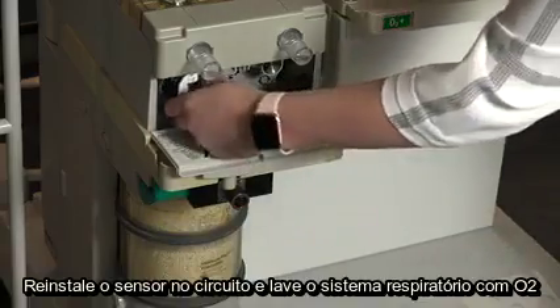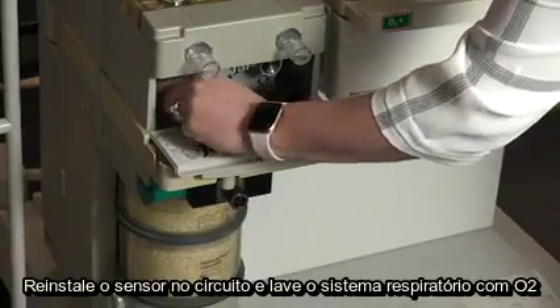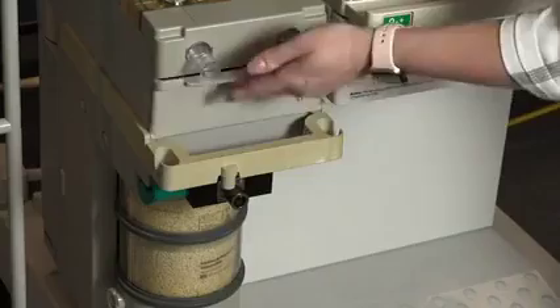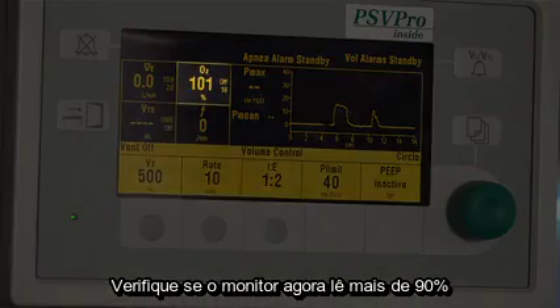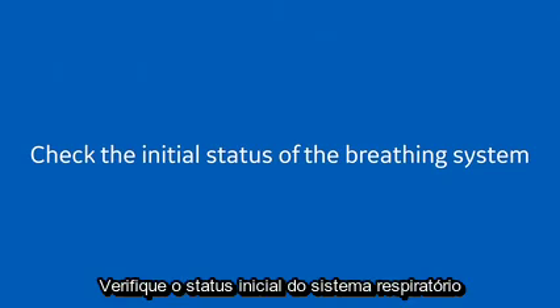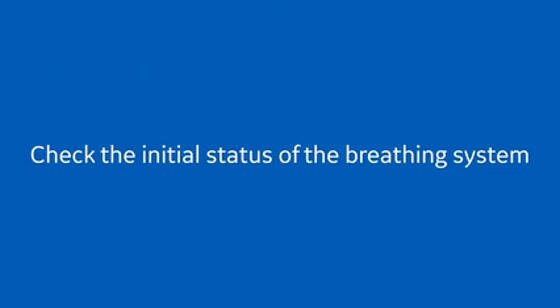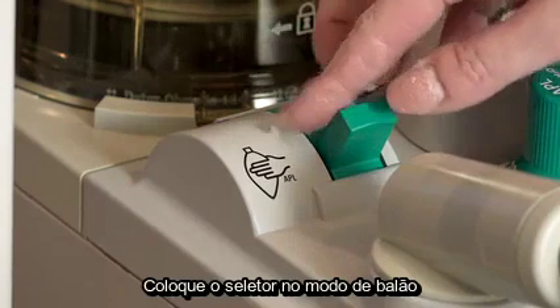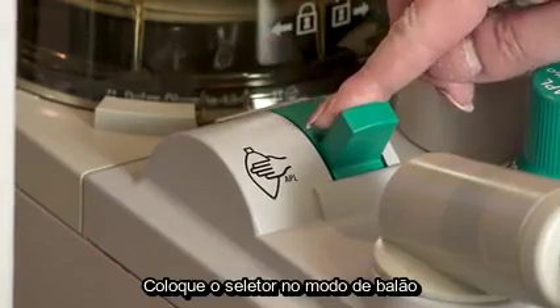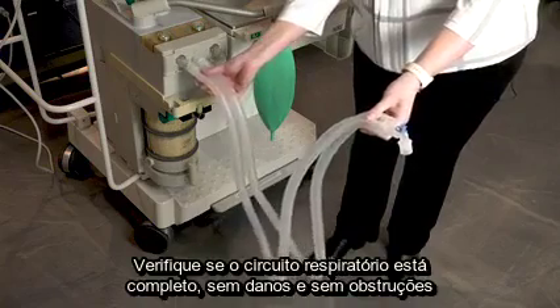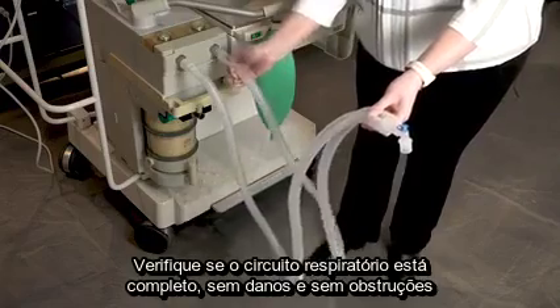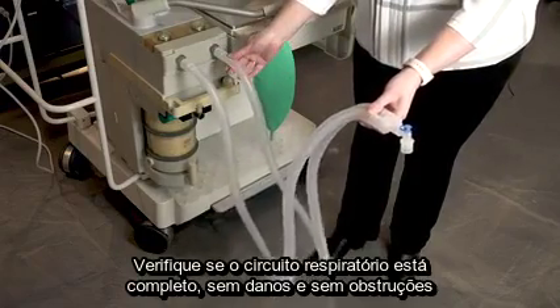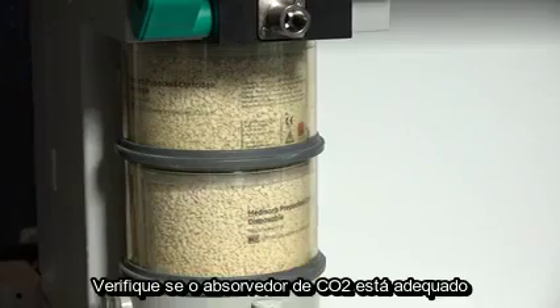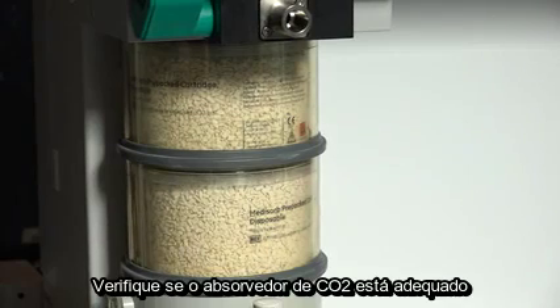Reinstall the sensor in the circuit and flush the breathing system with O2. Verify that the monitor now reads greater than 90%. Check the initial status of the breathing system. Set the selector switch to bag mode. Check that the breathing circuit is complete, undamaged, and free of obstruction. Verify that the CO2 absorbent is adequate.